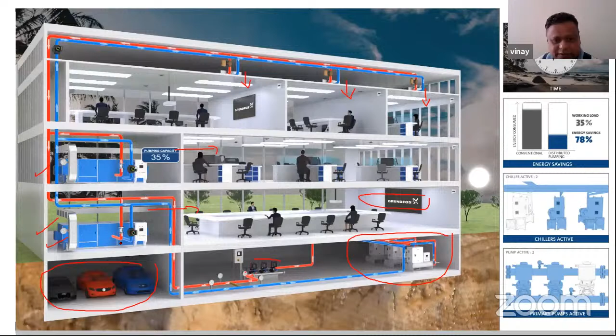When the cold water is passed through the coils and you have blowers or the fan, it will get cold air, or in the winter you can get hot water instead by replacing the chiller with boilers. This is a typical example in India, where you have the chillers, the pumps, the air handling units, and the fan coil units. This conditions the air for the system. On the right side, these are the primary pumps, which circulate water throughout the building. Some of the chillers save energy, which is important for sustainability, and we'll show that shortly.